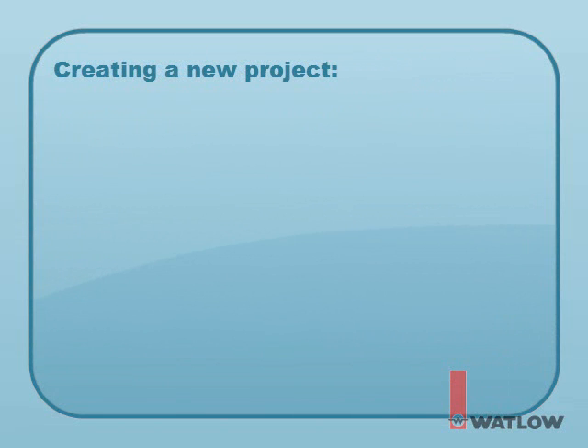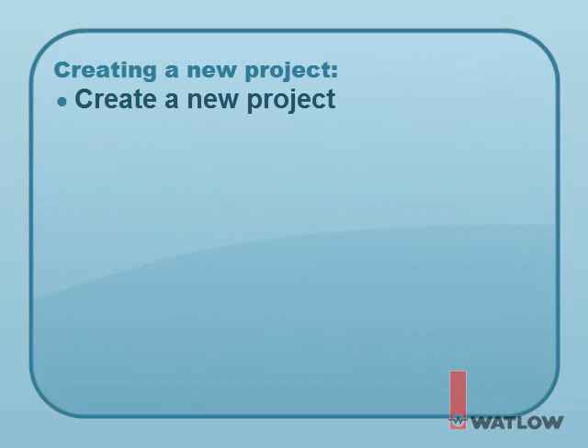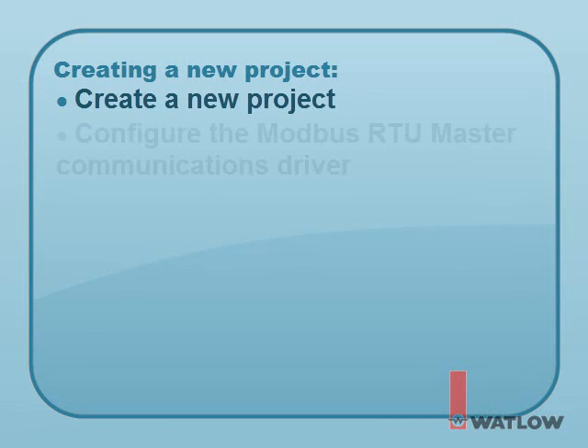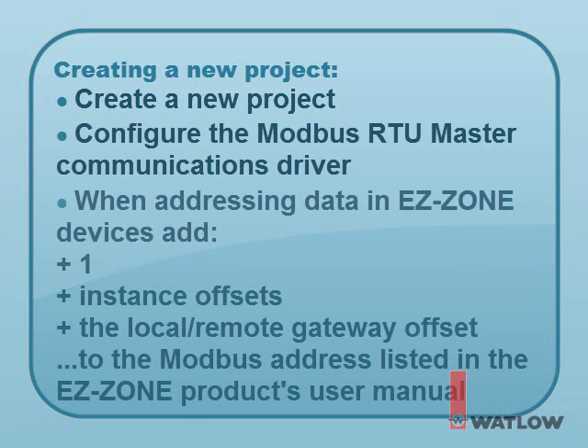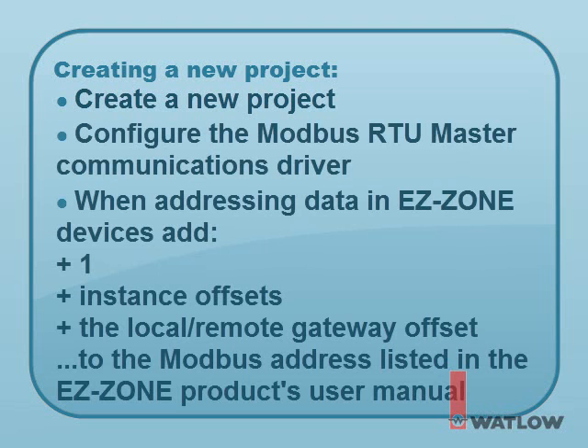The steps for creating a new Silver Series project that communicates with EZZone products via Modbus RTU gateway are create a new project in EasyBuilder 5000, configure the Modbus RTU device that appears by default with the correct COM port and Modbus communication settings, and remember, when addressing data in EZZone devices, add 1 plus any instance offsets plus the gateway offset to the Modbus address found in the EZZone users manual.